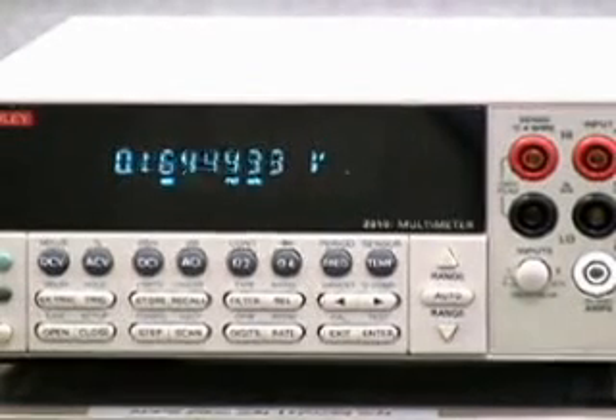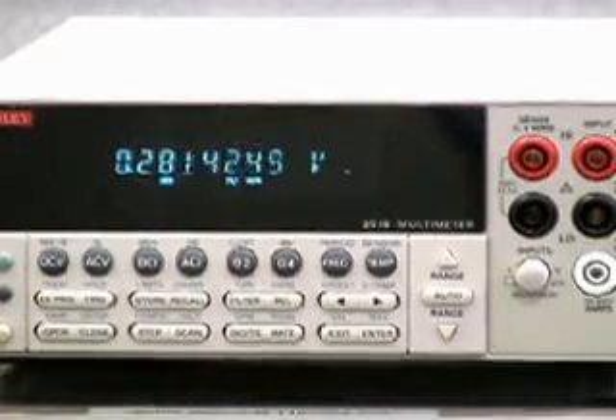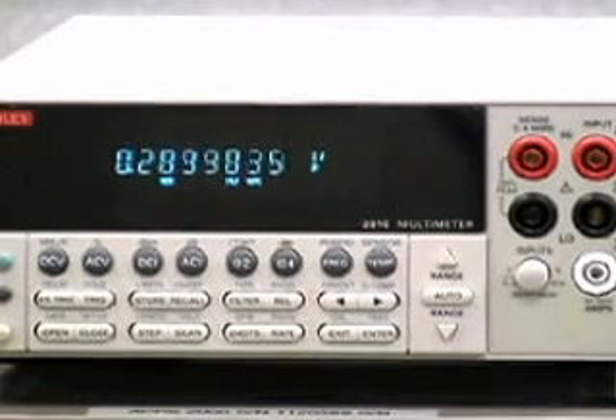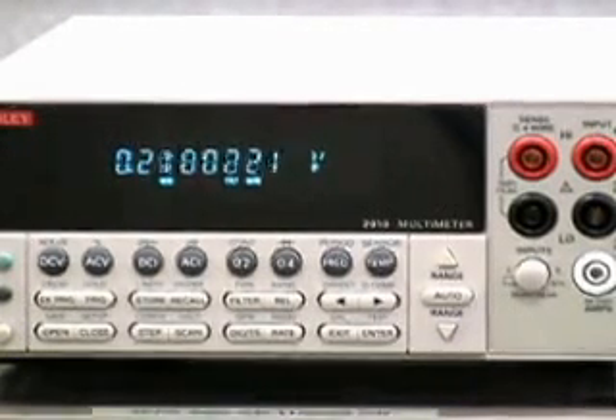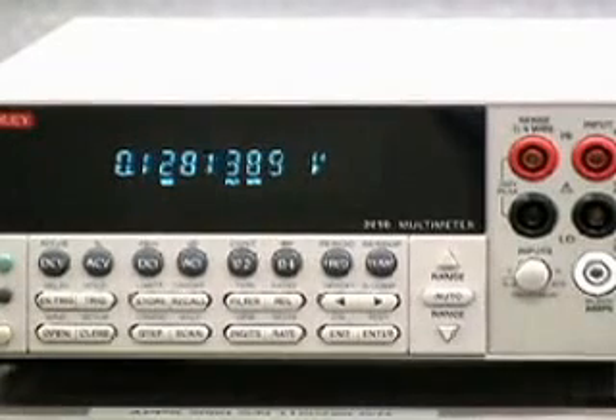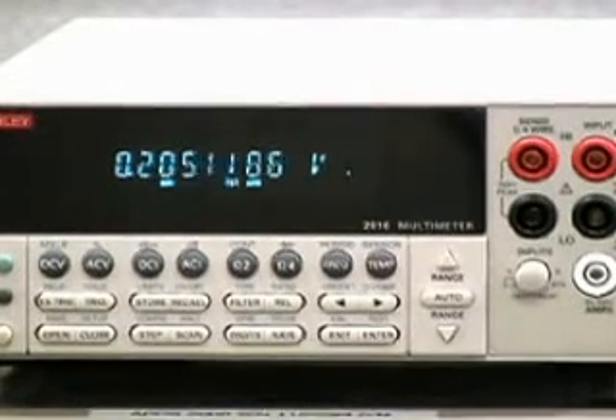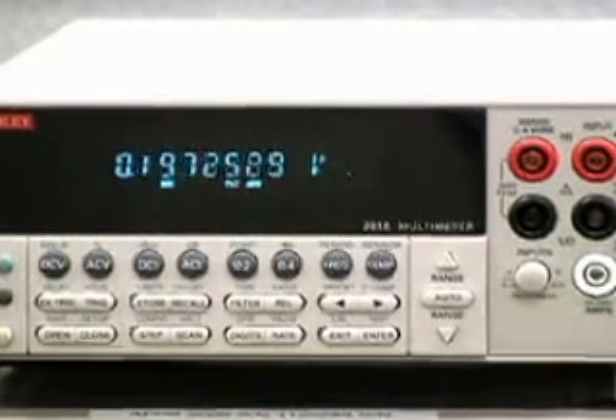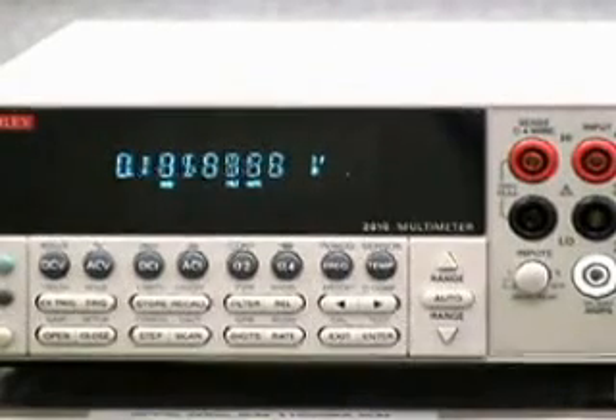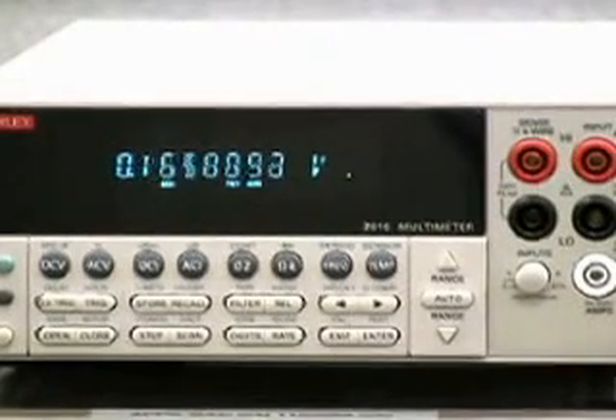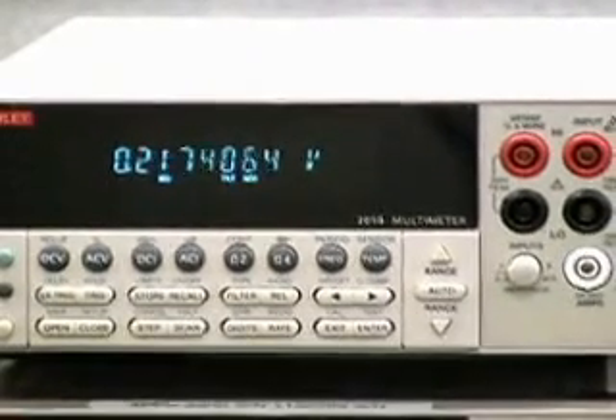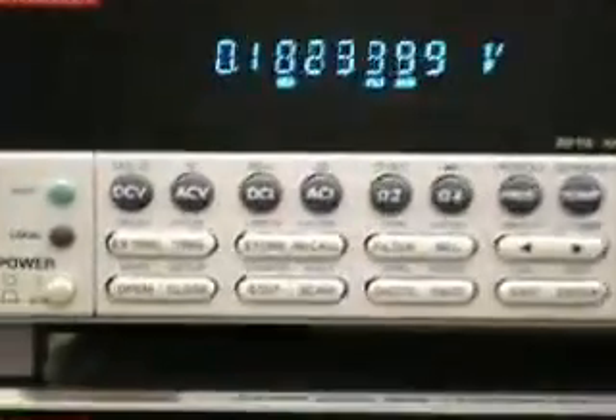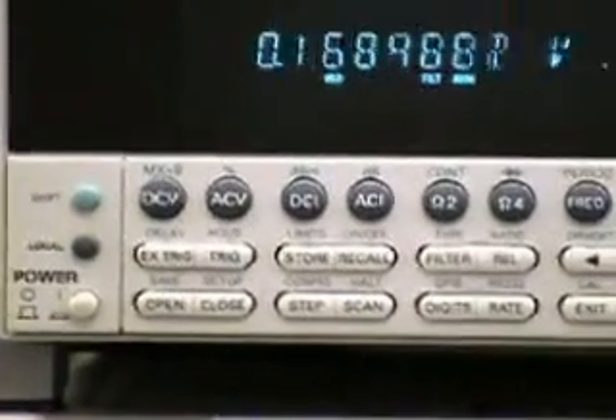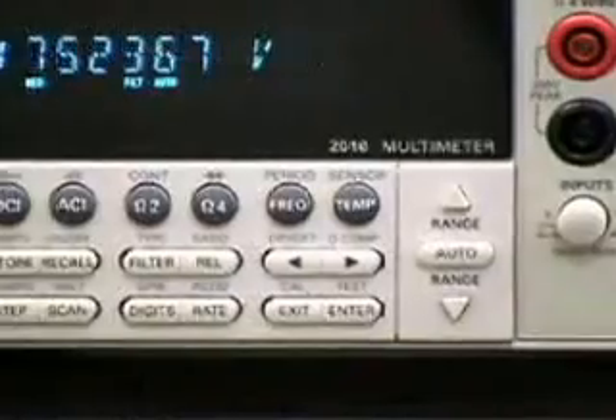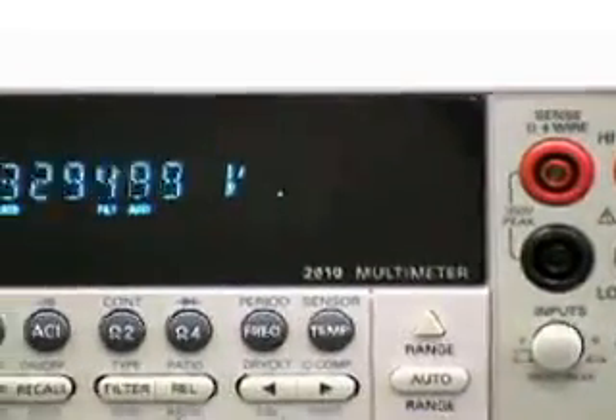It can also measure temperature, but the main difference here is it'll measure temperature with the three types of thermocouples, J, K, and T, but also RTDs, which are resistance temperature detectors. That gives you a far more accurate type of temperature measurement. One of the key features of the 2010 is its low noise capability. By low noise, I mean it's extremely quiet.